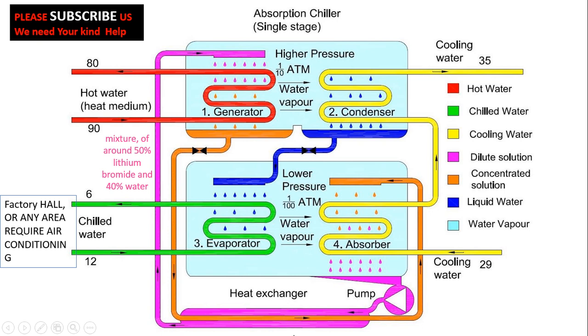Before the recombined lithium bromide and water solution is pumped back to the generator, it passes through a heat exchanger. This heat exchanger recovers some energy to improve efficiency — allowing the solution to gain some heat before entering the generator, saving a small amount of energy. This completes the full cycle of the absorption chiller.